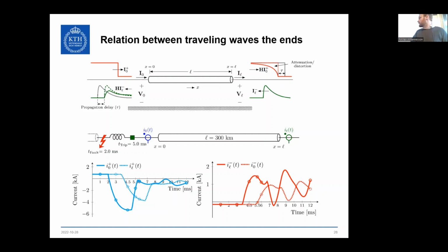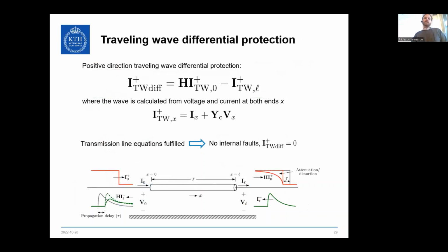Yeah, it starts at 2 milliseconds when the fault applies, and then it arrives on the other side a little bit later. So translating this into a protection would mean that you calculate the wave on the sending end, and then you calculate the wave at the receiving end. And by applying the propagation function to the sending end, you will estimate the wave that will arrive at the other side. And by calculating the difference, you will get this I TW diff, which should be 0 always for all conditions, as long as the transmission line equations are fulfilled.